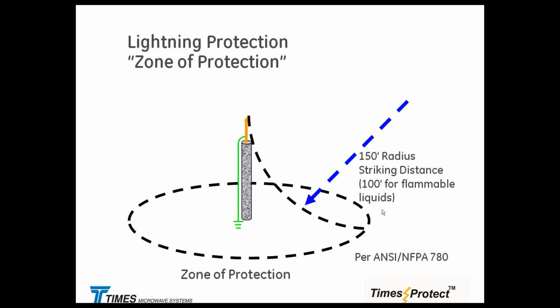So when we are modeling, the radius is going to be directly proportional to the amount of current and charge associated with that step leader and with the event, the peak current as we described in the previous statistical graph. So all we are doing right here, by extending the tower height, is trying to put the side-mounted antennas into that so-called protected zone. And if you take a look at the Ben Franklin rod or the lightning diverter rod, it's very sharp on the tip. There is a reason for it. You want to build the corona, to start that streamer going right on the top of that guy, as opposed to having the corona being launched from the side, from the panel antenna or any type of antenna on the tower, from any other sharp object. So the reason for that sharp Ben Franklin rod is to basically start the streamer flowing this way. So as the step leader comes down, you are basically looking at current flowing through the tower, not through the antennas and coaxial cables into the equipment.